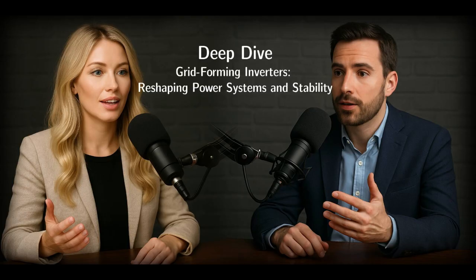On the protection system side itself, we're seeing increased use of communication-assisted schemes, like line current differential, which are less dependent on fault current magnitude. Adaptive protection is key: systems that can automatically change their settings based on which resources are online. We're also exploring alternative principles, like those based on voltage or traveling waves, and developing methods for coordinating the response of multiple grid-forming resources across a wider area.